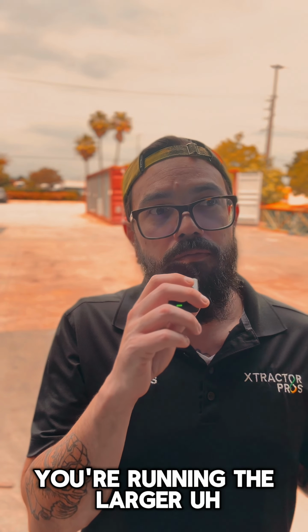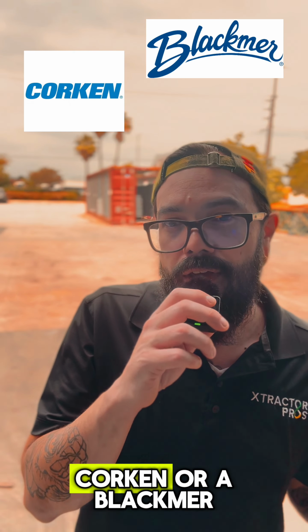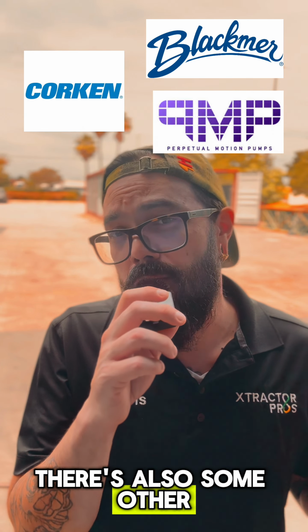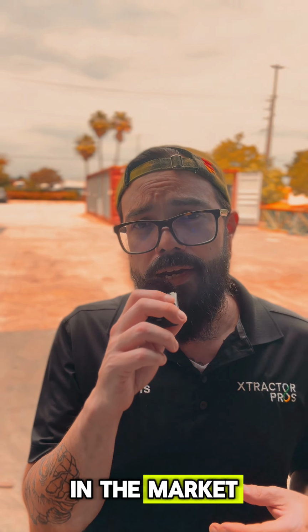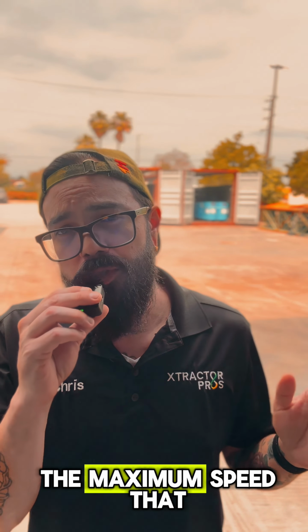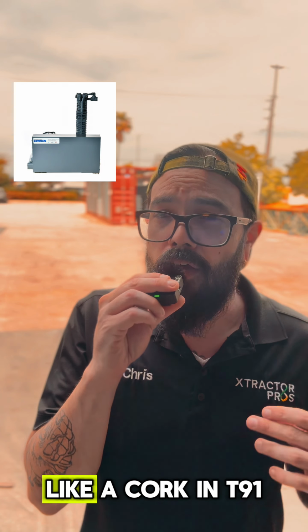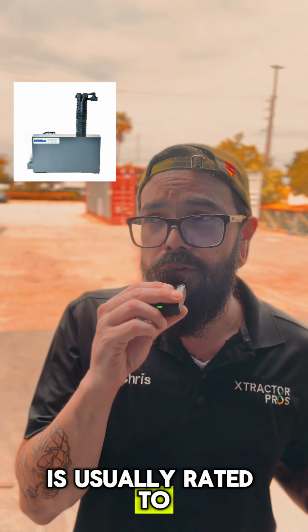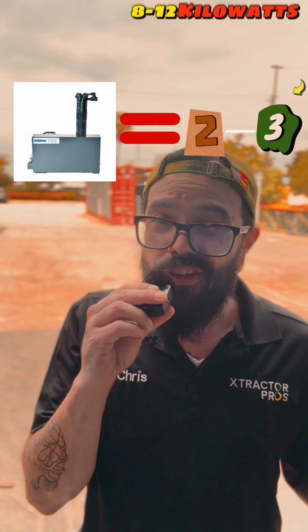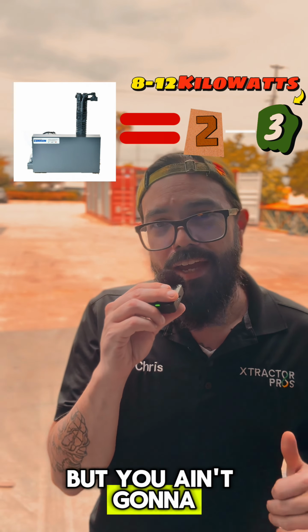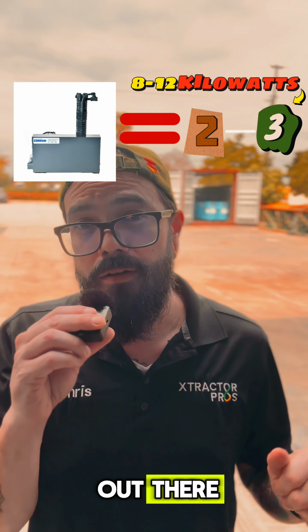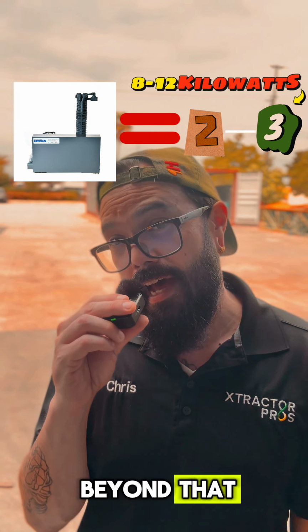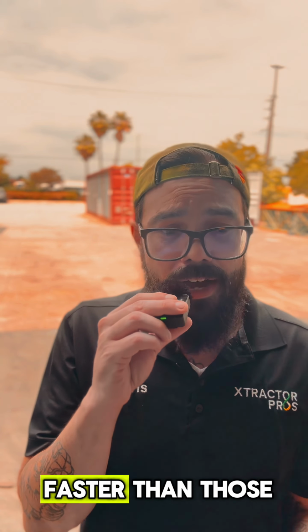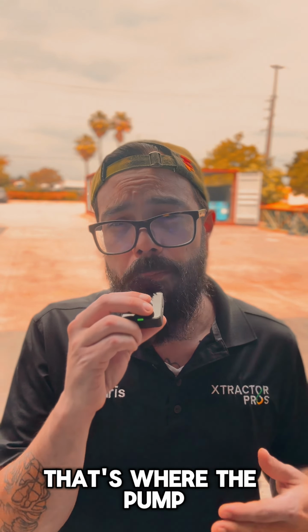If you're running active recovery with the larger gas compressors like a Corken or a Blackmer, and there are also some other brands of gas compressors on the market now, you want to be hitting the maximum speed that they are rated for. A Corken T91 is usually rated to about 2 pounds a minute. You could probably push it to 3, but you aren't going to get any faster than that. It's just going to top out there. No matter how hot you heat it beyond that, the pump is not going to pump any faster than those pistons are moving. That's where the pump becomes a variable.